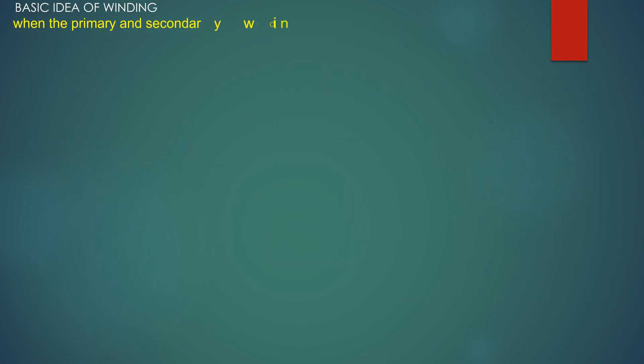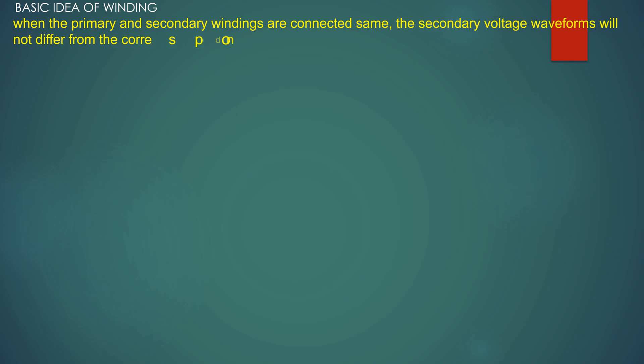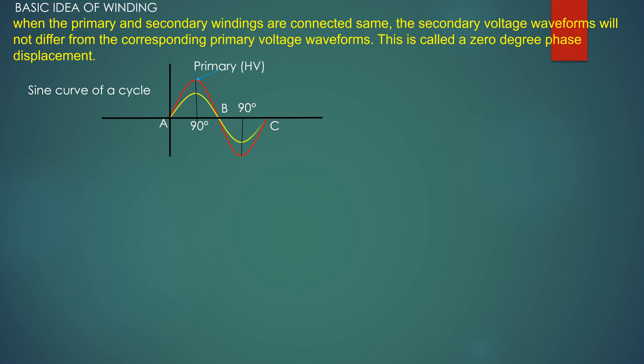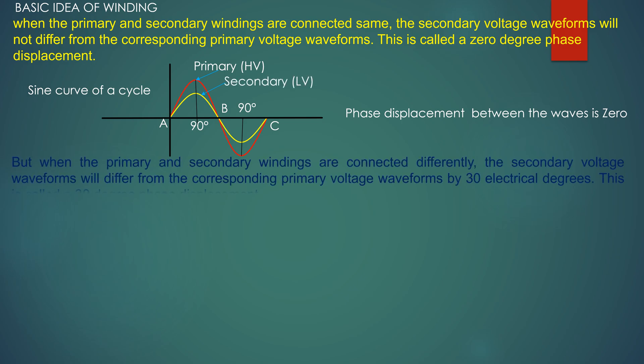When the primary and secondary windings are connected the same way, the secondary voltage waveforms will not differ from the corresponding primary voltage waveforms. This is called zero-degree phase displacement. But when the primary and secondary windings are connected differently, the secondary voltage waveforms will differ from the corresponding primary voltage waveforms by 30 electrical degrees. This is called a 30-degree phase displacement.